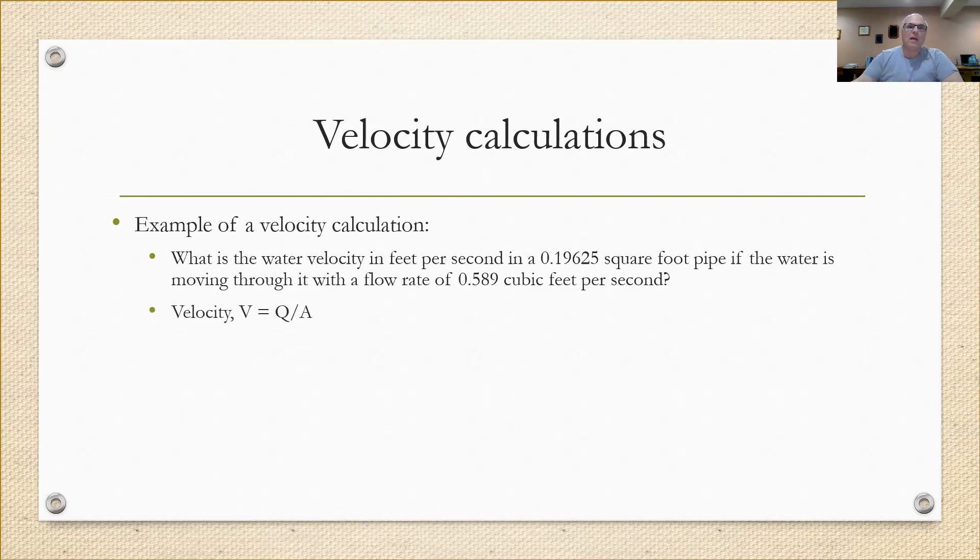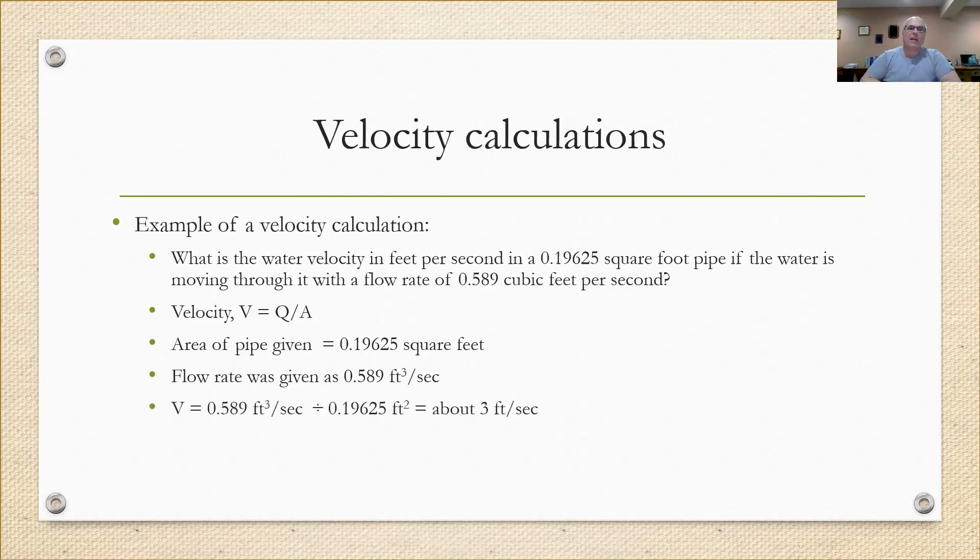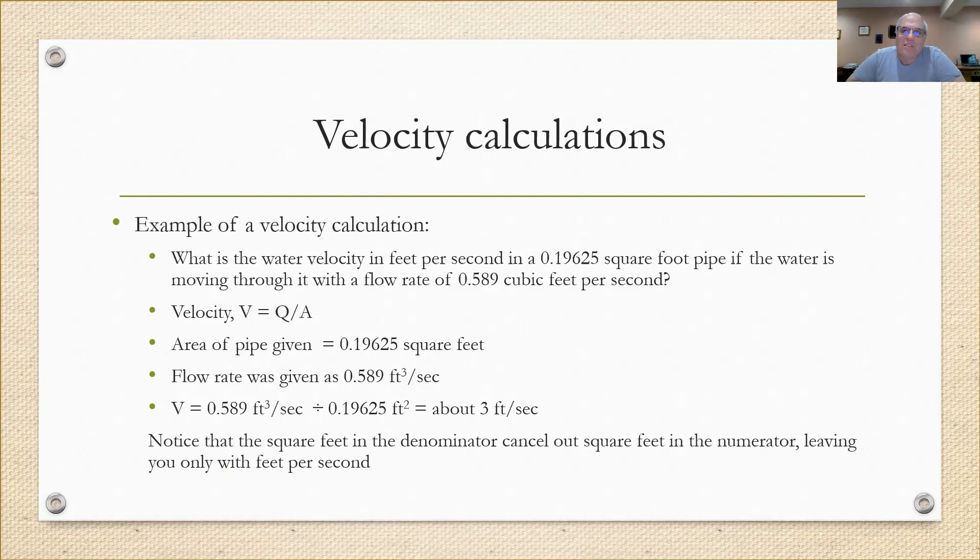We're going to use the velocity equation, V equals Q divided by A. The area of the pipe was given as 0.19625 square feet. The flow rate was given at 0.589 cubic feet per second. It's just a matter of plugging in the numbers. The velocity is 0.589 cubic feet per second divided by 0.19625, which comes out to about three feet per second. Typically when engineers design pipes for velocity, they try to be somewhere between one and five feet per second. So if you come out with 50 feet per second, maybe you've done your math wrong.